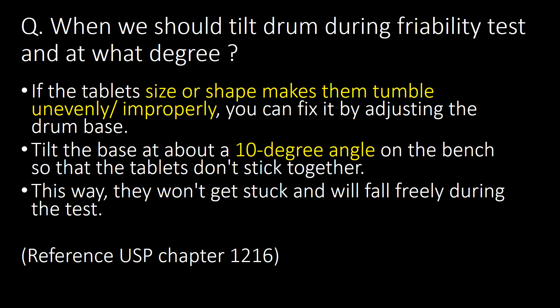When should we tilt the drum during the friability test, and at what degree? If the tablet's size or shape makes them tumble unevenly or improperly, you can fix it by adjusting the drum base. Tilt the base at about a 10-degree angle on the bench so that tablets don't stick together — this way they will fall freely during the test.